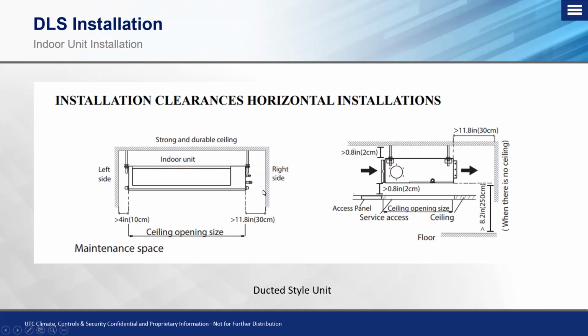Now on the right side where your refrigeration connections are, we're going to need at least 12 inches minimum of space to get in there to access those service fittings, not only for the initial install, but also on the back end if we have to go back in and repair a leak. On the opposite side, which has the drain connection on there, you at least need to have 4 inches. Typically, I'd say 12 inches is more than enough on each side on there, but in tight applications, the minimum for service clearance to get in there would be 4 inches on the left-hand side, and on the right-hand side with our refrigeration connections, at least 12 inches.